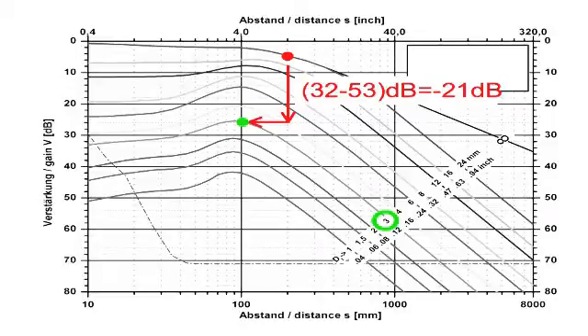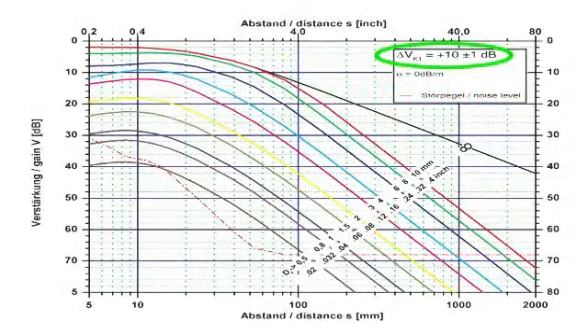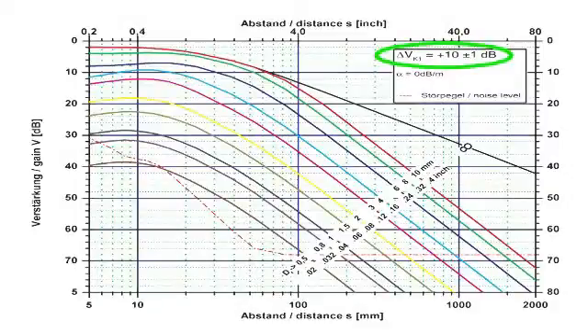When angle beam probes are used with the DGS method, normally there are no back walls available that are oriented perpendicularly to the sound beam. For this reason, one frequently uses the cylindrical surfaces of the standard reference blocks V1 and V2.